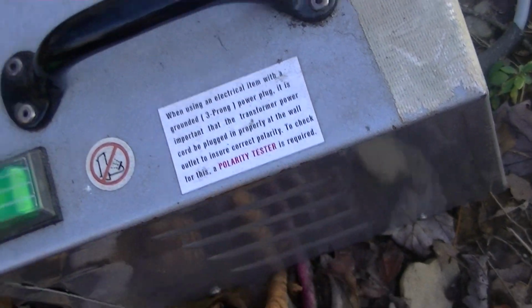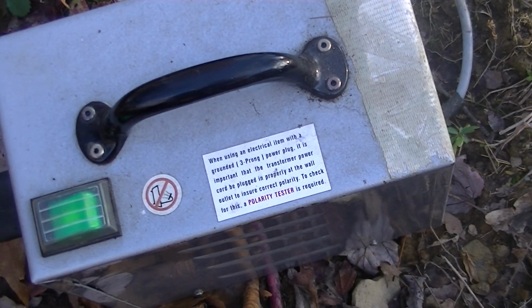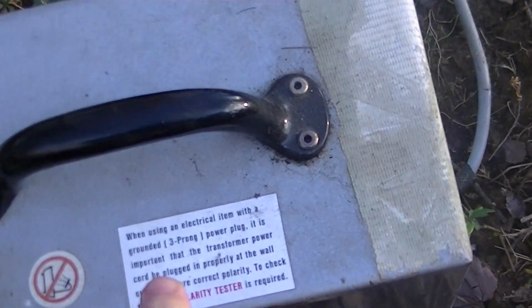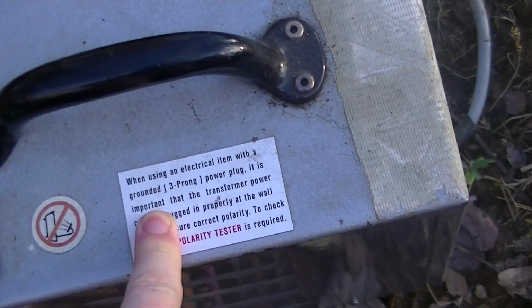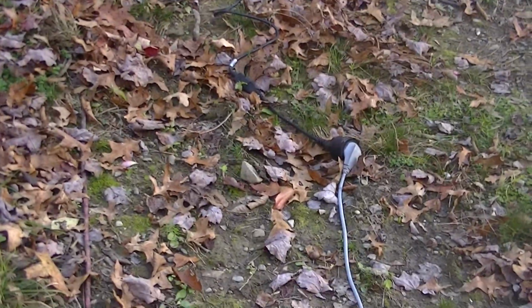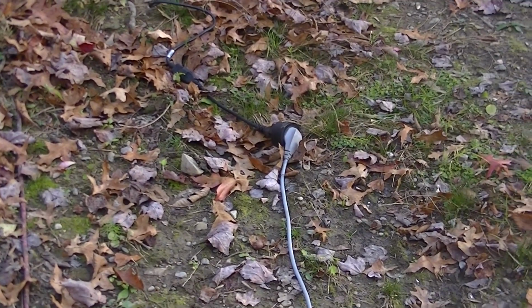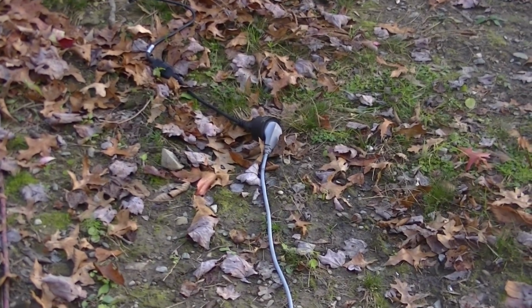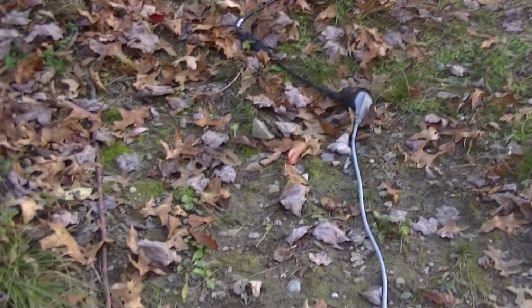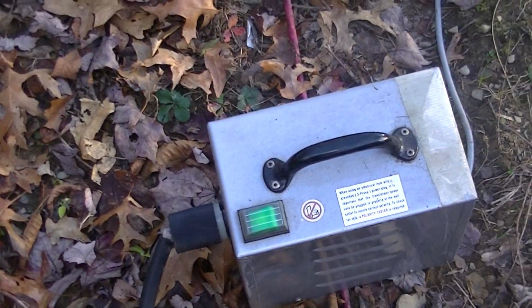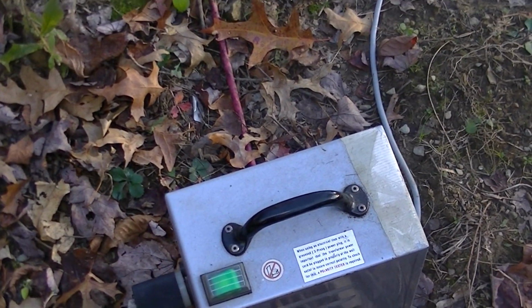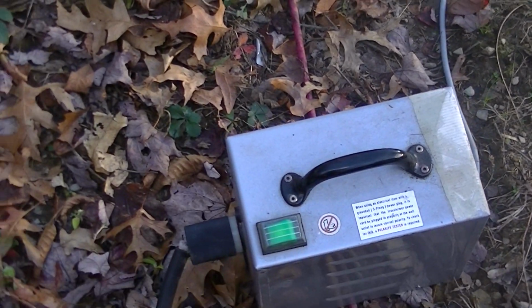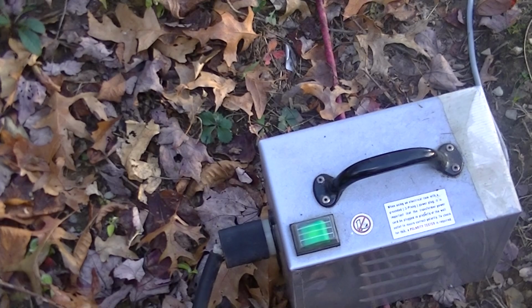And things barely even warm, although there is some fairly pronounced magnetostrictive vibration. And the warning on that is just because the Schuko plug, well, technically it's I think IEC 7/7 or whatever it is, isn't inherently polarized, and so either current carrying conductor can be the hot or the neutral, depending on how the plug's inserted. And because this is an autotransformer, depending on the polarity, well, phasing I should say, not polarity, the neutral, quote-unquote, could be sitting at 220 to 230 volts or something like that.